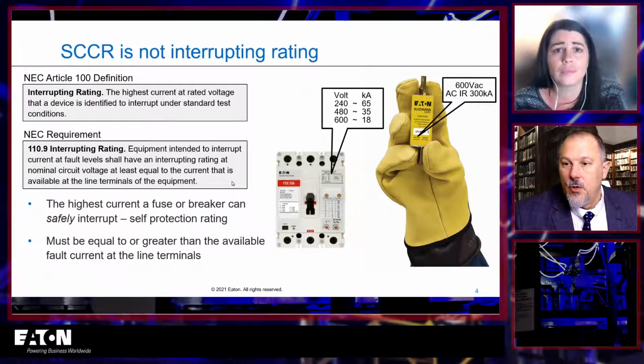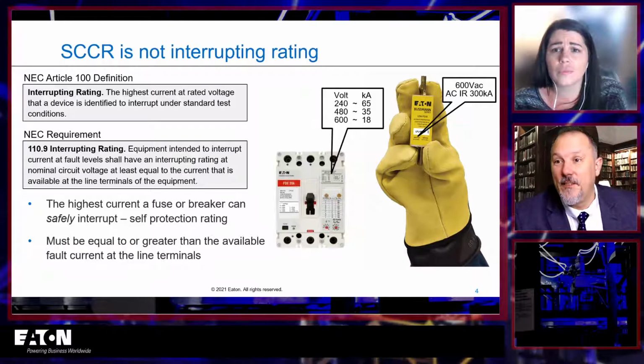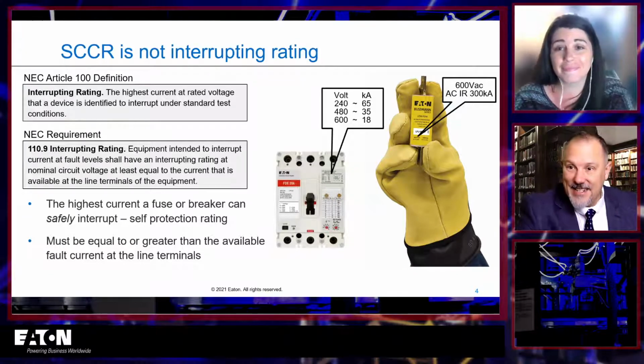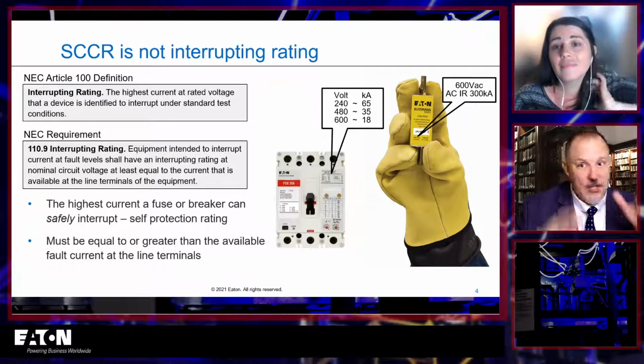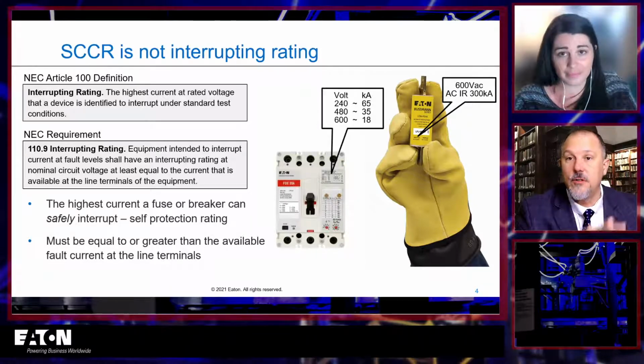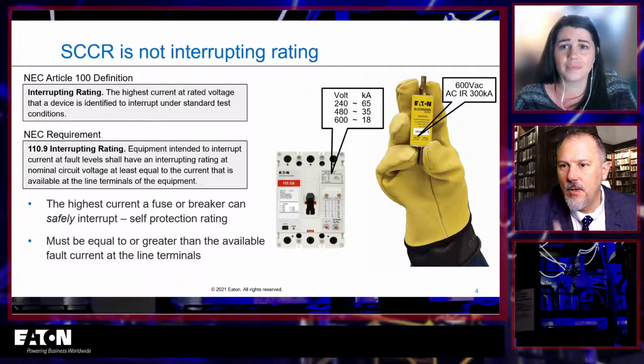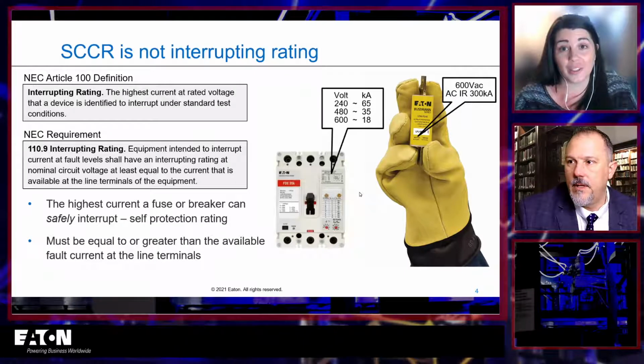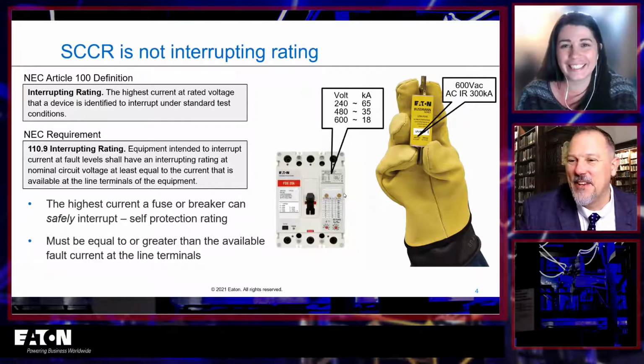We haven't even gotten off of, Sharice brought up SCCR versus AIC, and those are two different things, which I think is what you're going through right now. This is interrupting current. Exactly. And we'll get to the enclosure and the ratings. We'll get to 110.10, that's your withstand rating, very shortly. We can't even get off the second slide. Yeah, we're just getting in order here.